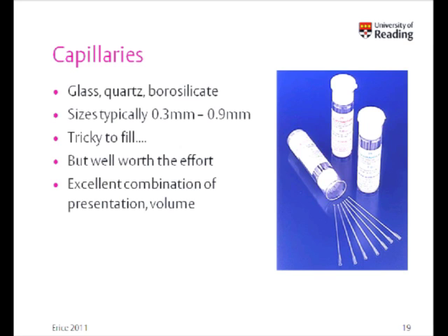There's all sorts of tips and tricks out there for how to fill capillaries, ranging from scooping up the powder in the top and then tapping it with your finger to rubbing a file on it. Our own personal favourite is one that Dave Cox showed me at the NSLS many years ago, and that is putting the capillary inside an empty shell of a cheap biro pen and then tapping it on the desk. Cheap, easy. And the most recent variant that I saw at Diamond was someone with an electric toothbrush encouraging some stuck powder to go down by vibrating it.